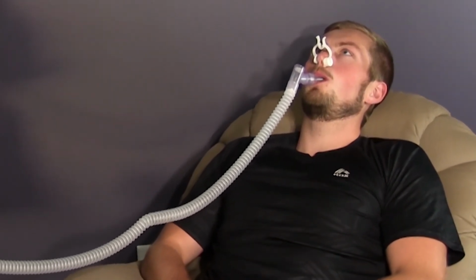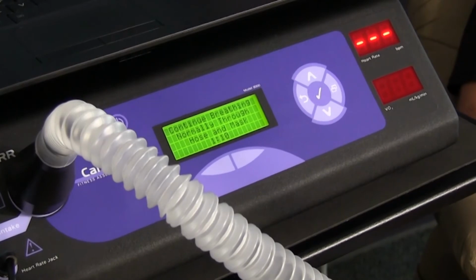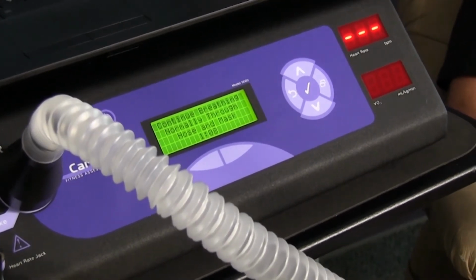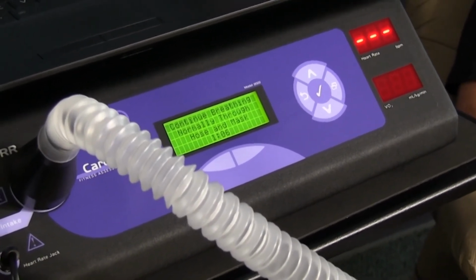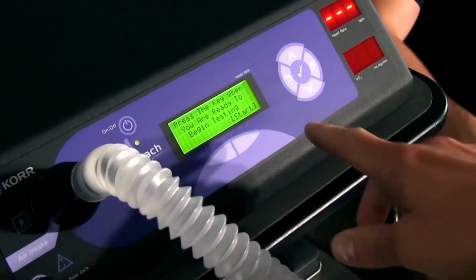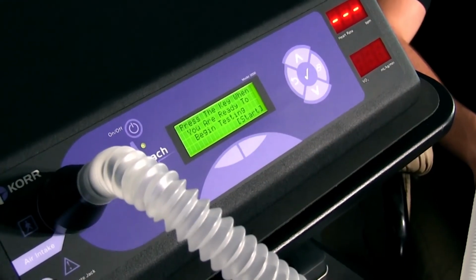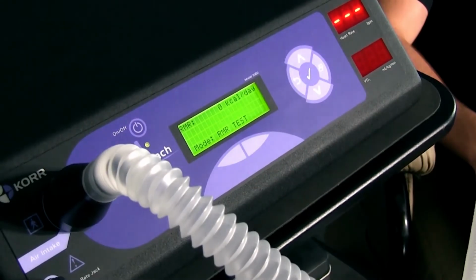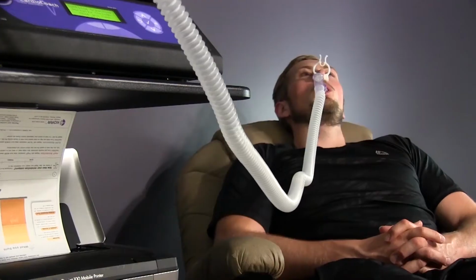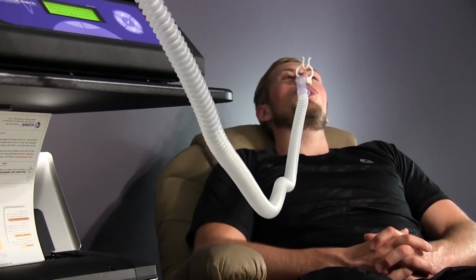Once the CardioCoach detects a breath, a time clock will appear on the LCD screen counting down from 1:30. When the countdown is complete, the machine will beep and you'll be ready to start the test. Press the check mark to start the test. Have your client breathe in a relaxed manner.